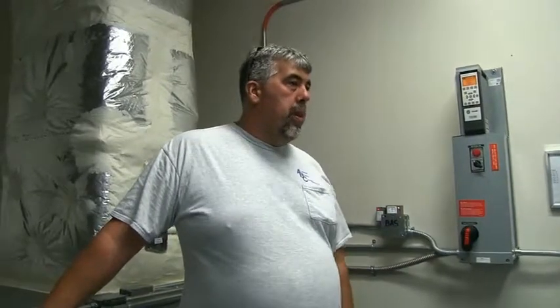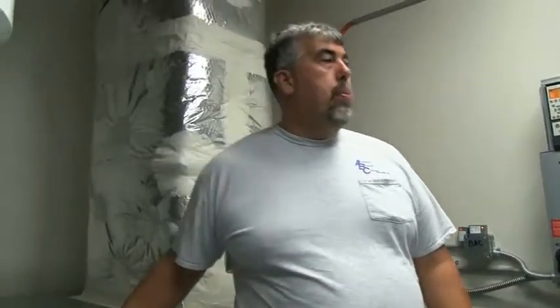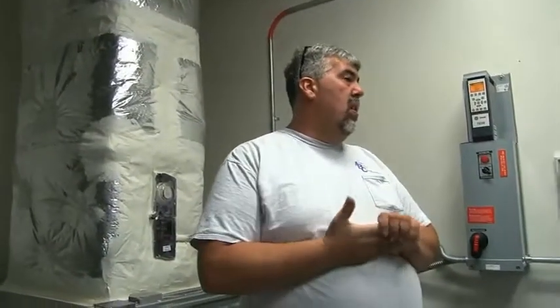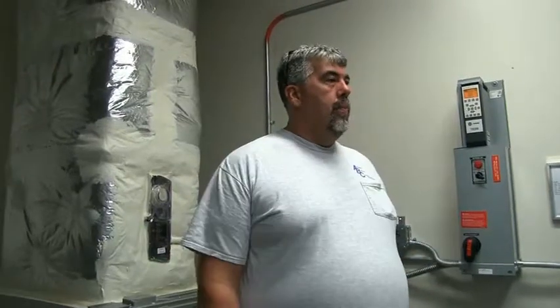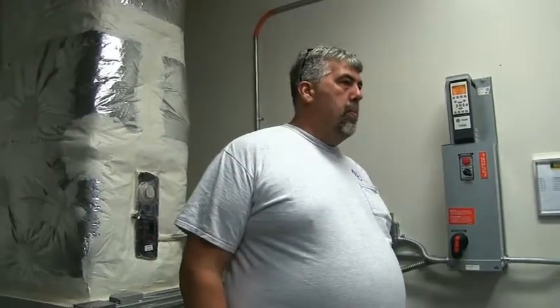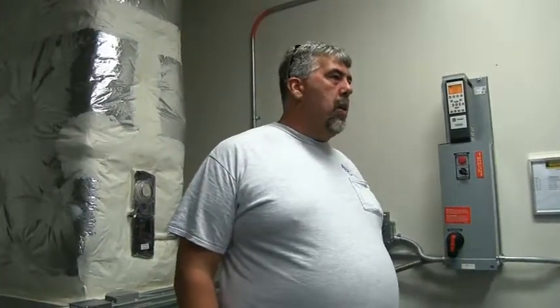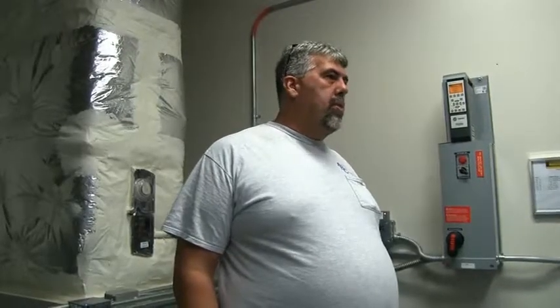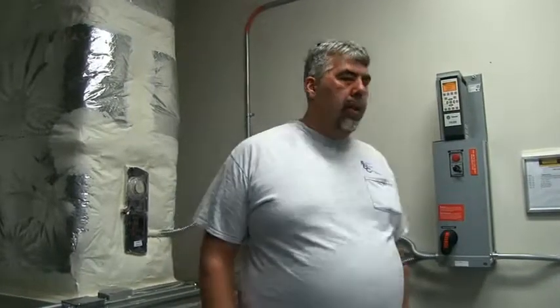For monitoring CO2 in the cafeteria, the cafeteria unit looks like this one, but operates differently. So it operates like a VFD box. So the CO2, is that just for monitoring, or is there a sequence for the CO2? As far as I know, that's just for monitoring. You could use a sequence for it with the outside air. But you would have to.